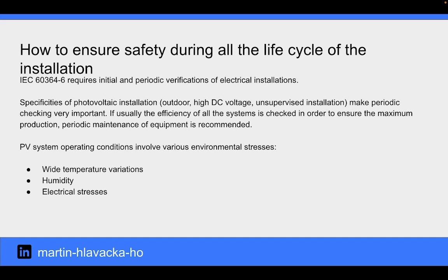IEC 60364-6 requires initial and periodic verifications of electrical installations. Specificities of photovoltaic installations make periodic checking very important. Usually the efficiency of all the systems is checked in order to ensure the maximum production, and periodic maintenance of equipment is recommended.